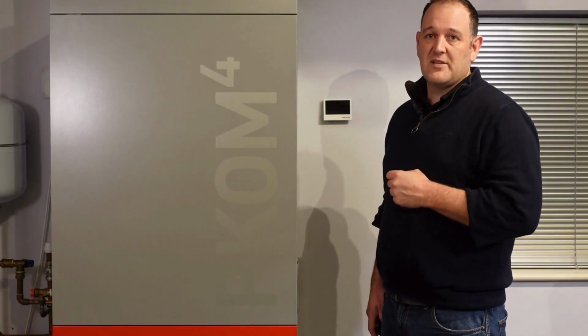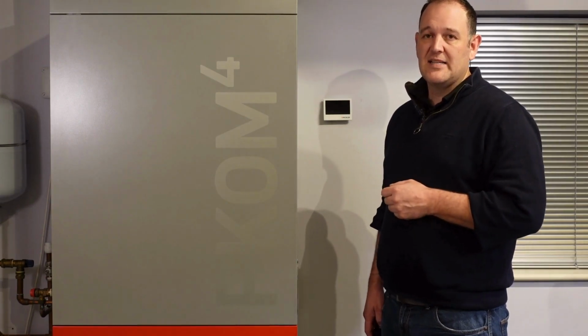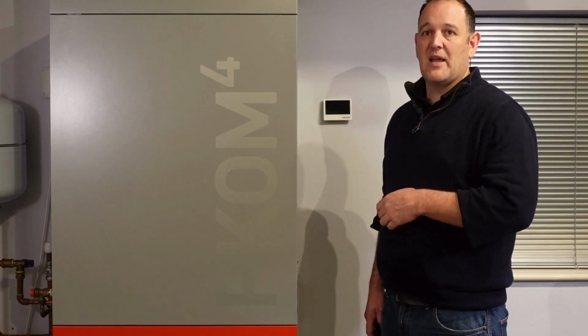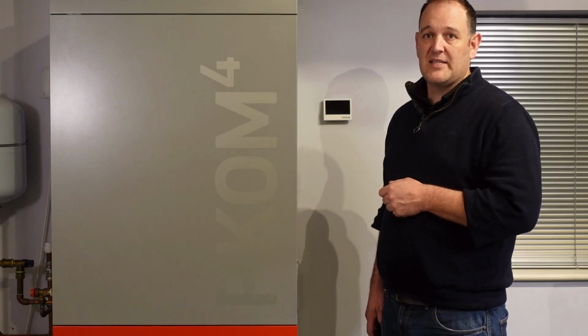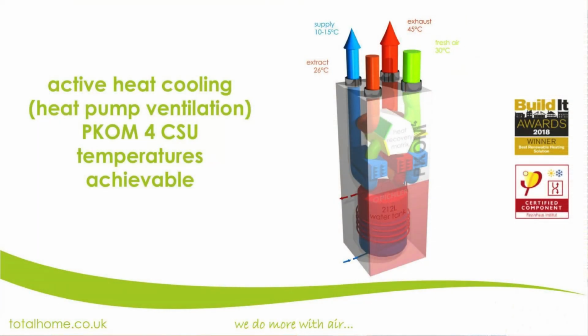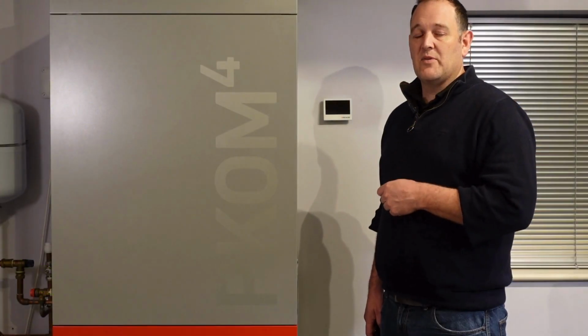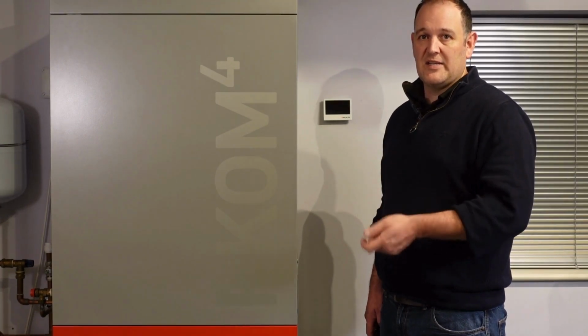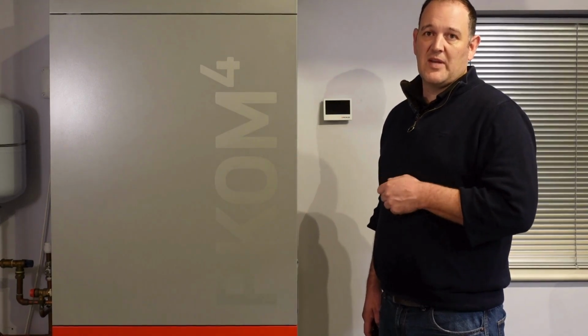The PKOM4 system is very low touch. It runs in the background. It takes care of the ventilation, your fresh air, your extracted air. It takes care of your space heating when needed. When there's a temperature fall in the property, it will help put extra heat into the place. In the summertime, if needed, the space cooling will come on if there's an overheat in the property, just to help reduce the temperature a couple of degrees. And it will also heat the domestic hot water. When you start drawing off hot water and it's replenished with cold, the heat pump will kick on and help bring that back up to temperature.